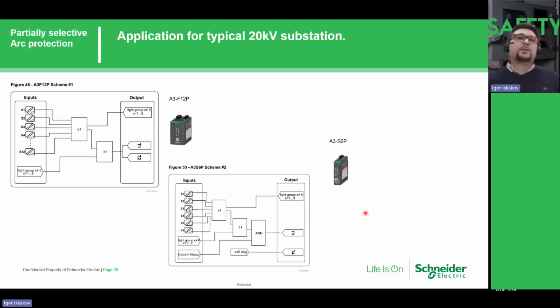So for this particular application, for example for A3 F12 units, we can choose scheme number 1, where any sensor will trip contacts, one being the incomer and the other the bus bar. They also receive the light from this A3 unit by group, for example group 1, and they will provide the same trip. And the A3 unit will also, on any sensor, send a command on light group 1 or 2. We will have one additional trip. For example, it can be used for the bus bar, or for the 110 kilovolt trip, like CBF protection. And we have self-diagnostic for the system.